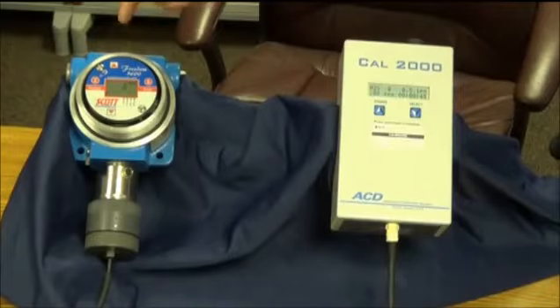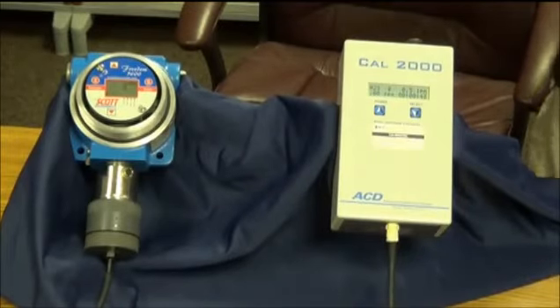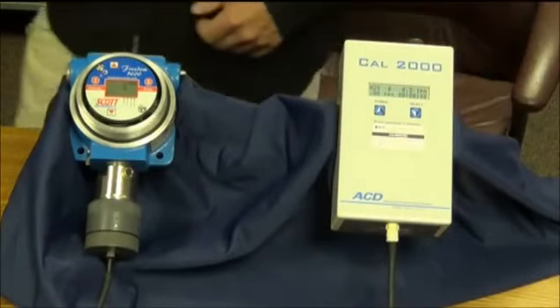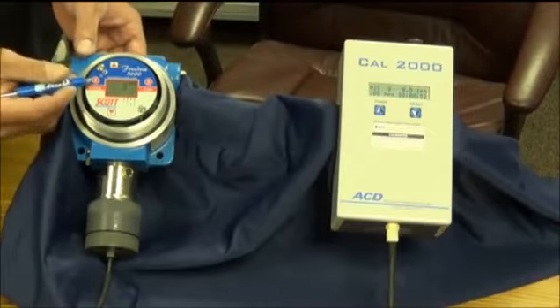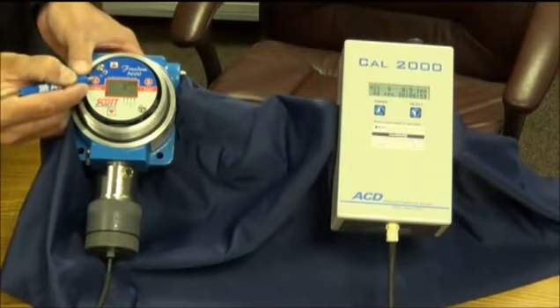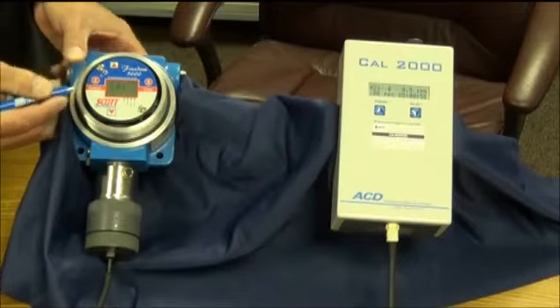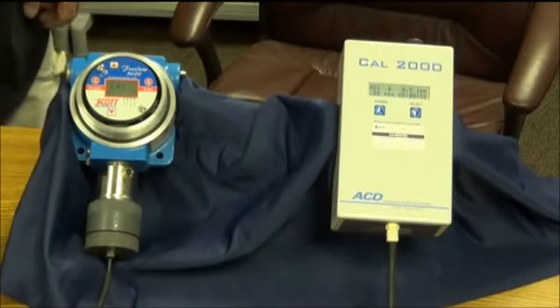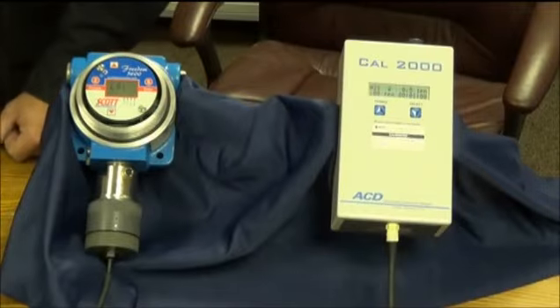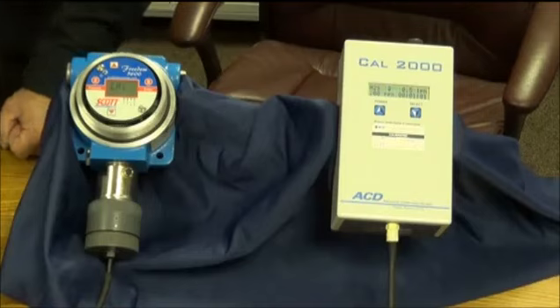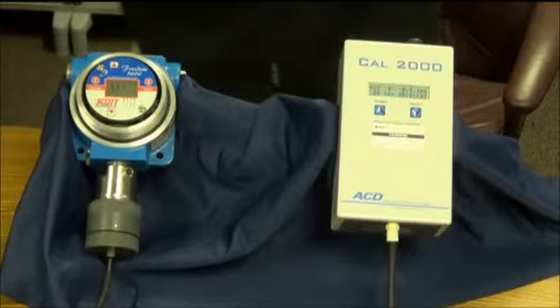Now what we're going to do is set 0 over here. This particular sensor is zeroed using a magnetic screwdriver. So I hold that screwdriver over the 0. It says Cal, and once it says set, we can move on to our calibration. Alright, so that's set at 0.